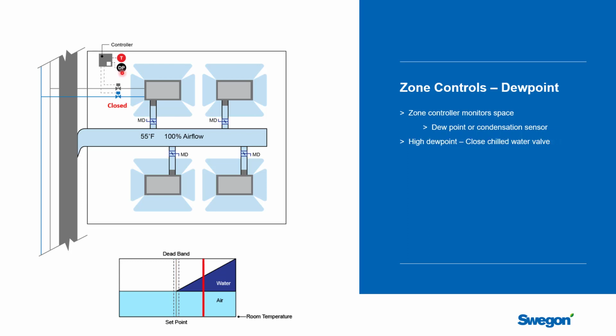But what happens if we start to have the dew point start to climb in the space? The most common approach to deal with this is to close off the chilled water valve. It's the chilled water that's going to be the coldest thing in the room. It is what would cause the piping to sweat. It's what would cause the coils to sweat. And so the solution is, if something's gone unusually wrong in the space and you sense that, close off the water to this control zone.